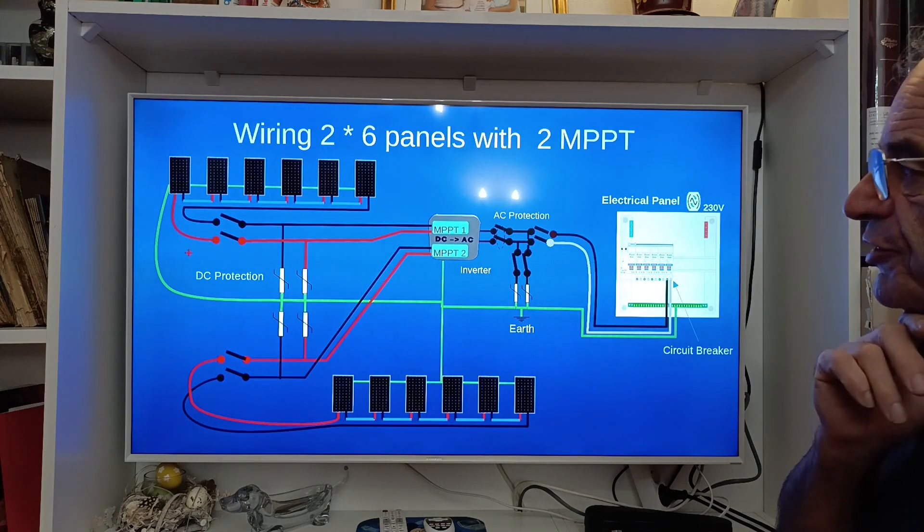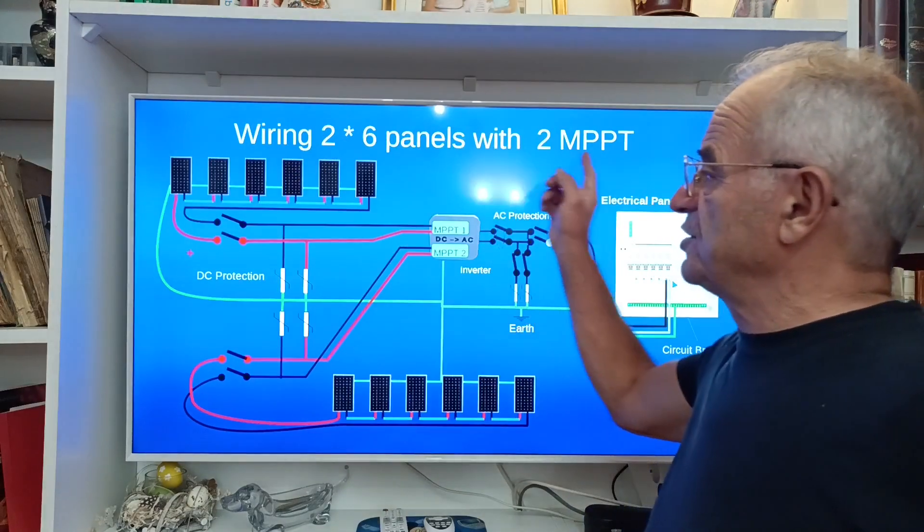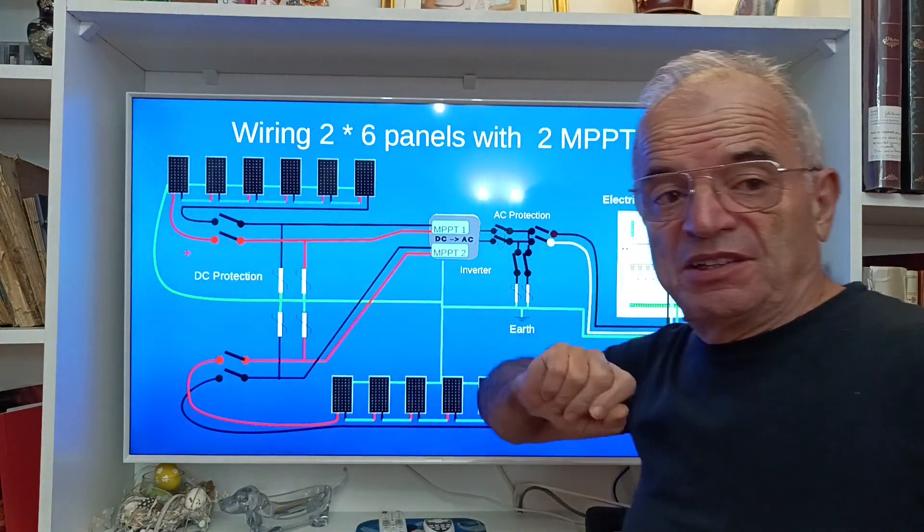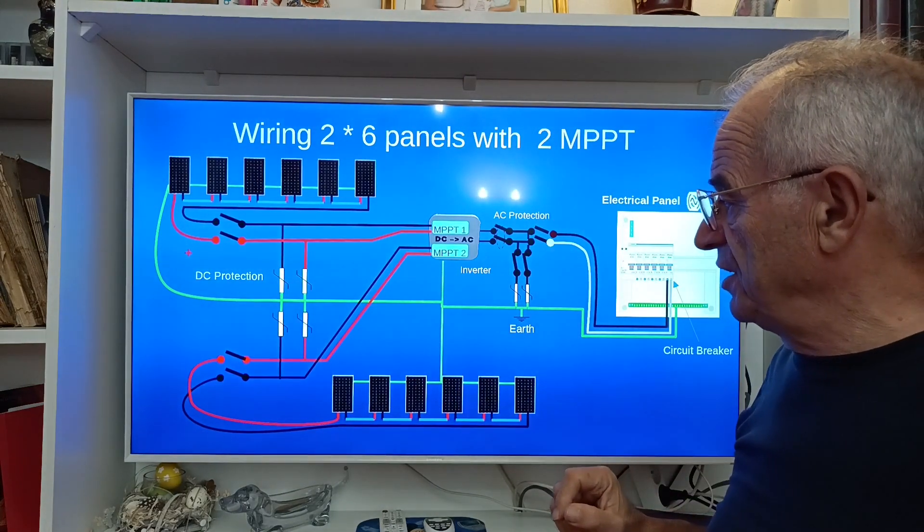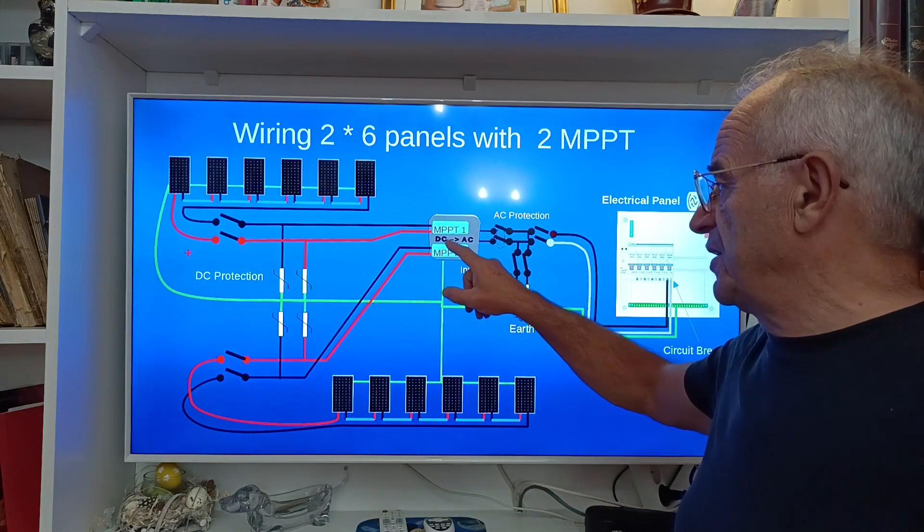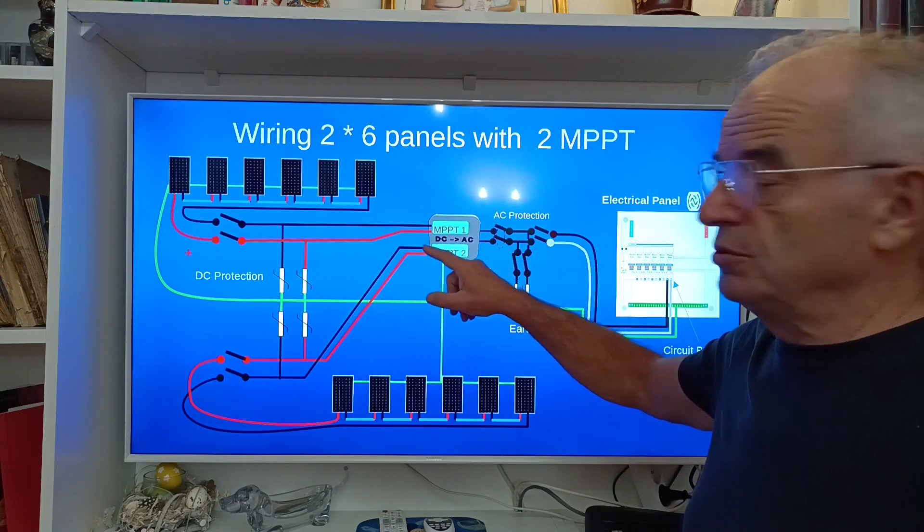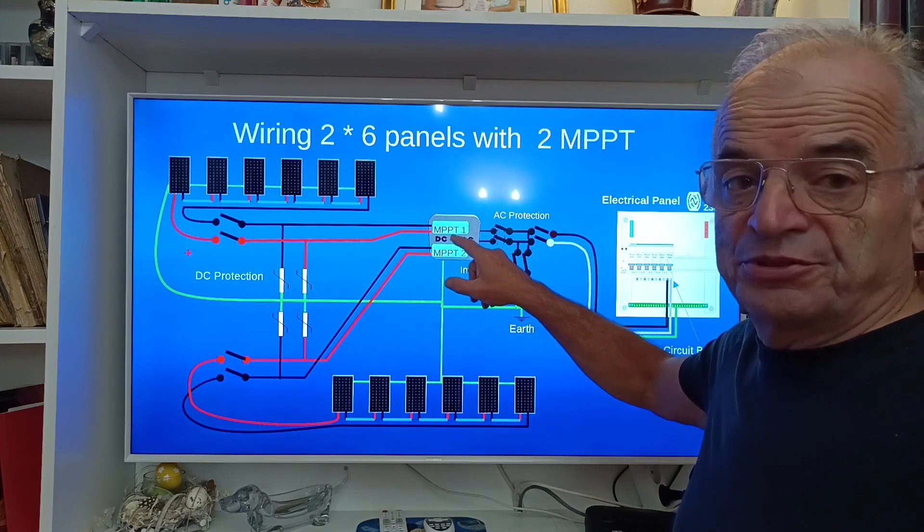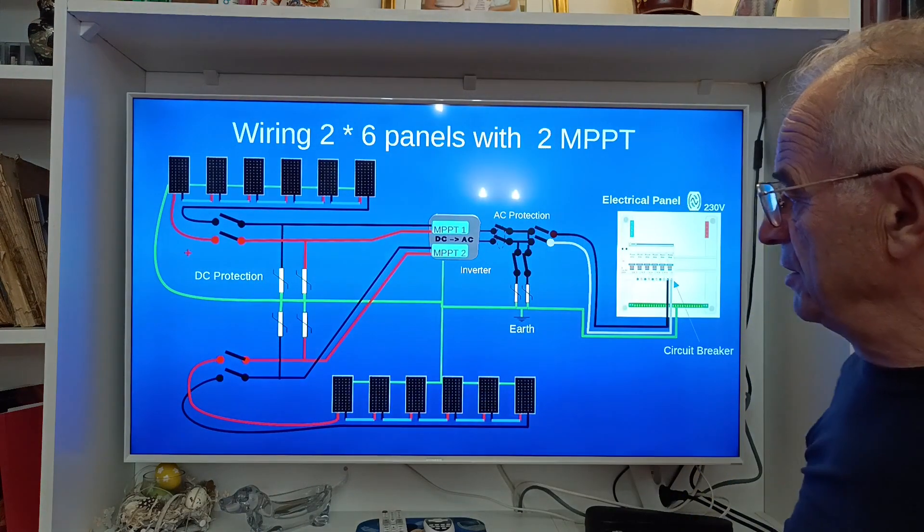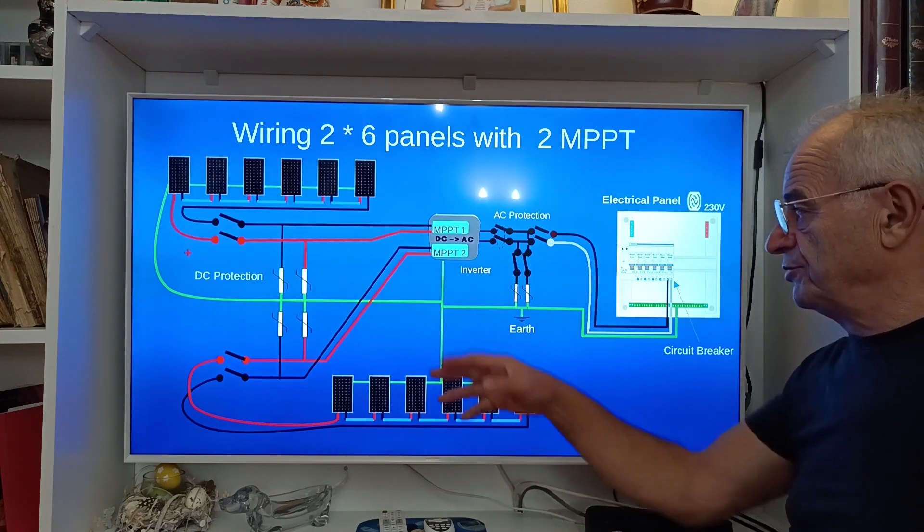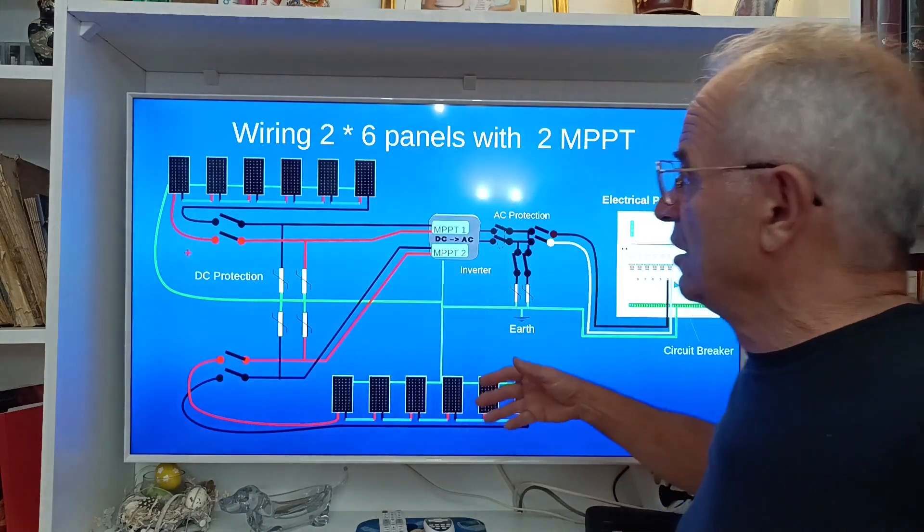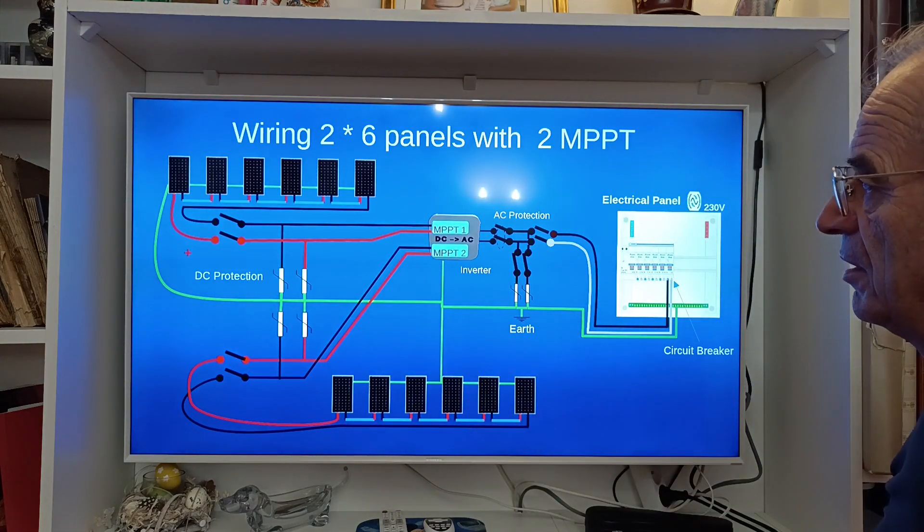Another interesting configuration is if you want to wire two times six panels. Two times six panels here, you can have all the six panels in serial as we have already seen, and here another group of six panels. And you have an inverter which has two MPPT trackers, two maximum power point trackers. So you can connect one to the group of six here, and another one to the group of six here. And for the rest, there is no difference. So it's a way to interconnect two different groups of panels.